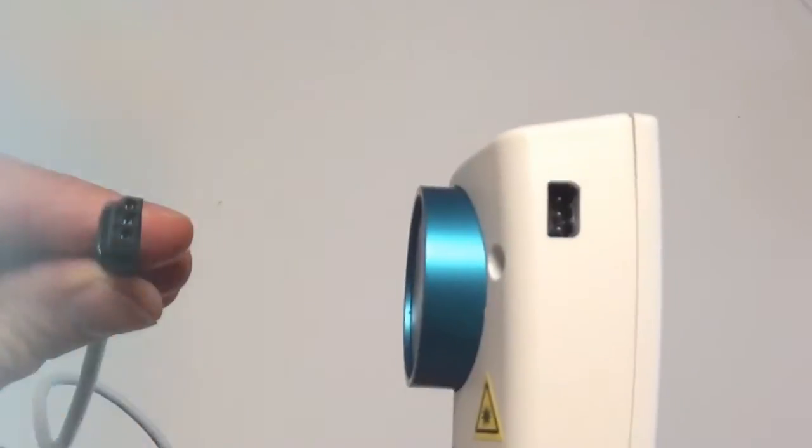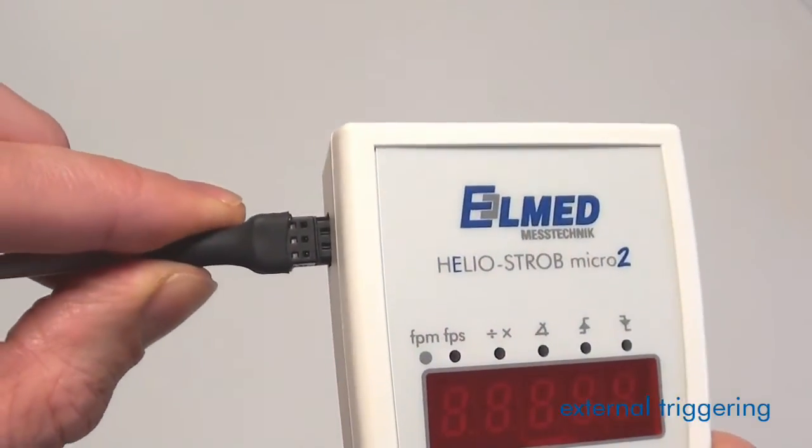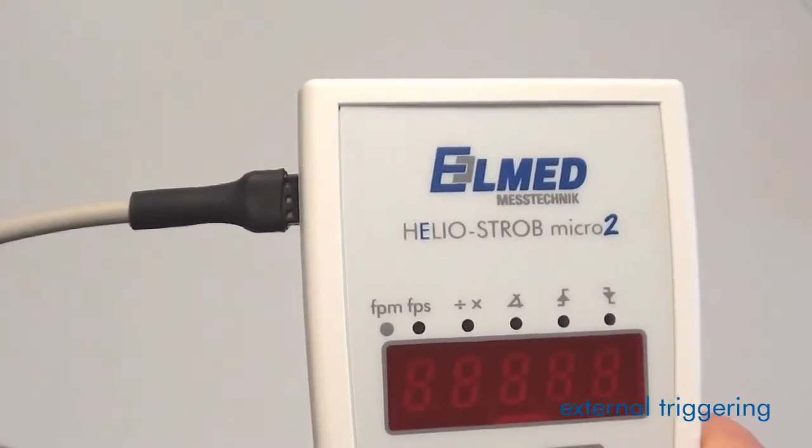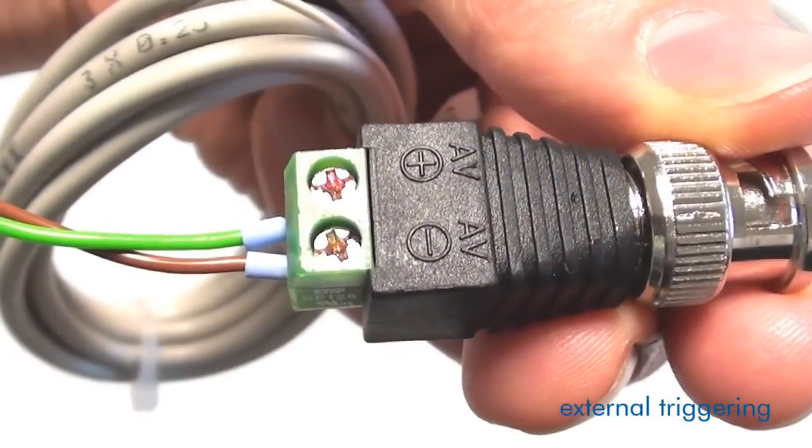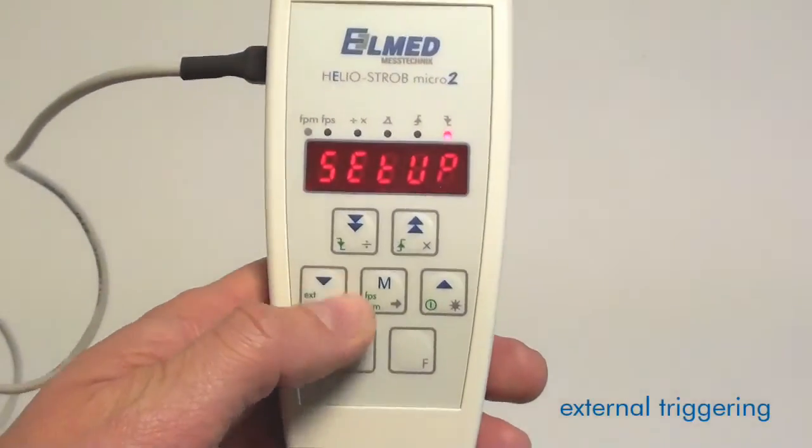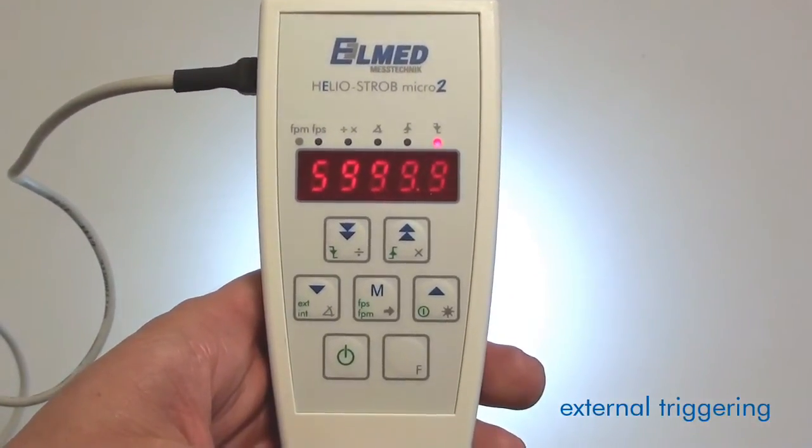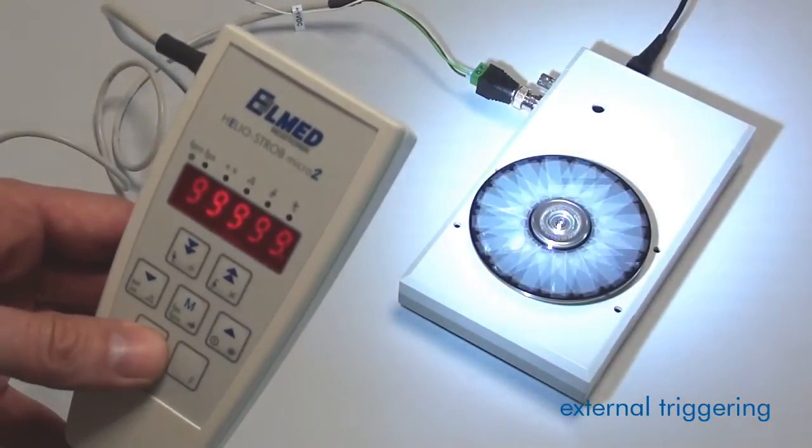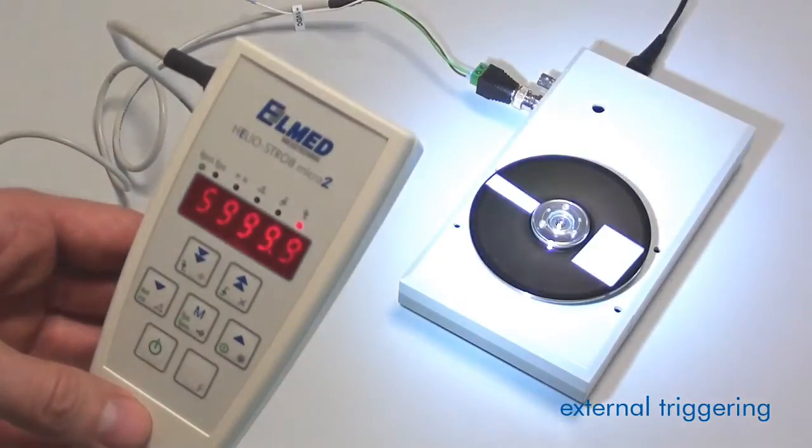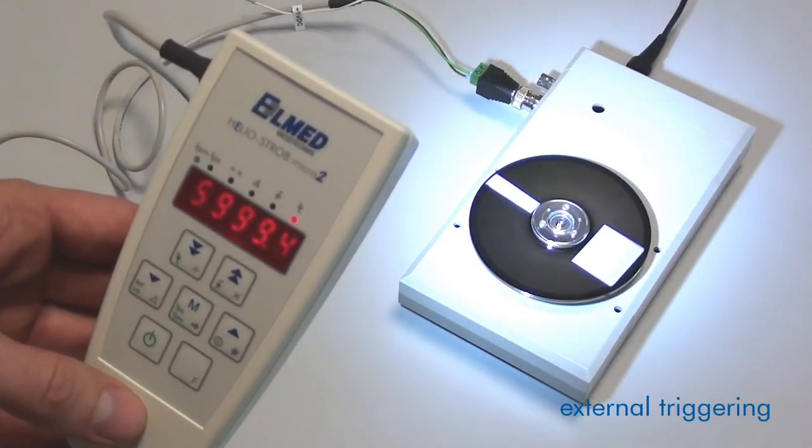The automatic synchronization of the flash rate with a moving object can easily be achieved by feeding an external clock. Use the trigger cable included in the delivery and, if necessary, the BNC adapter. By pressing the function key F and subsequently the COMMAND key EXTERN, you switch to the external triggering mode. As soon as an external clock is detected, the stroboscope flashes according to the frequency signal. It goes without saying that you can connect different industrial encoders. For this, the HelioStrobe Micro 2 provides a 10V supply voltage.